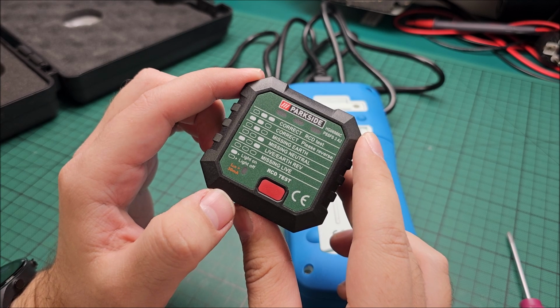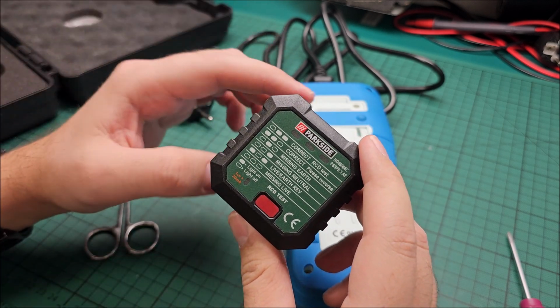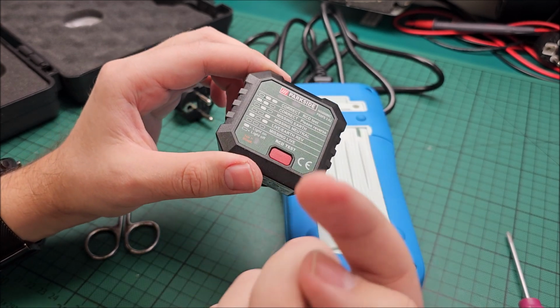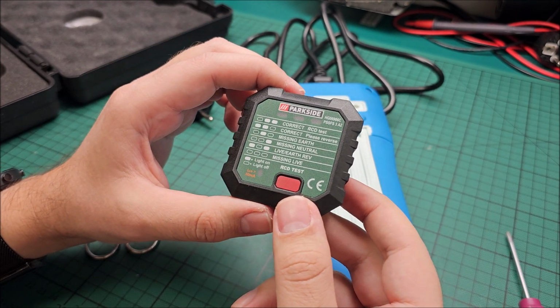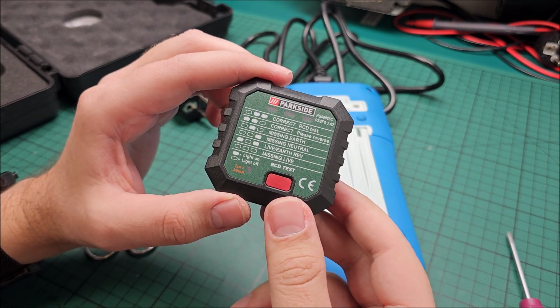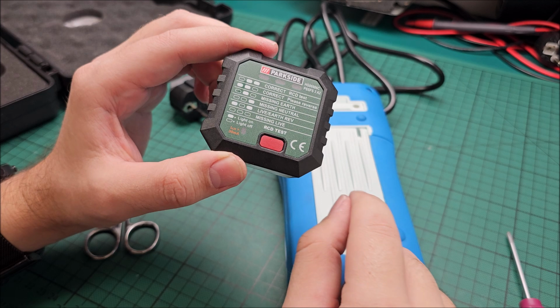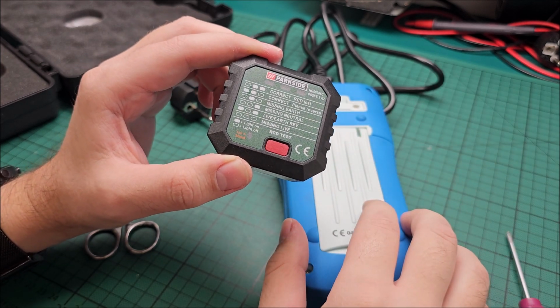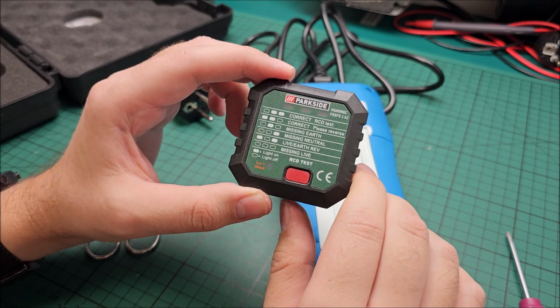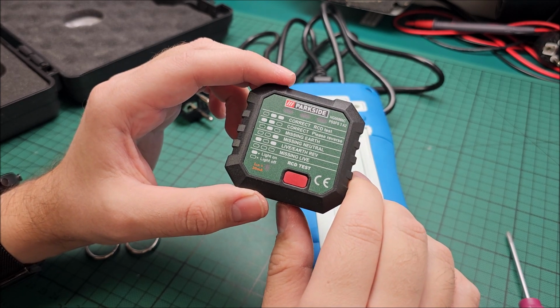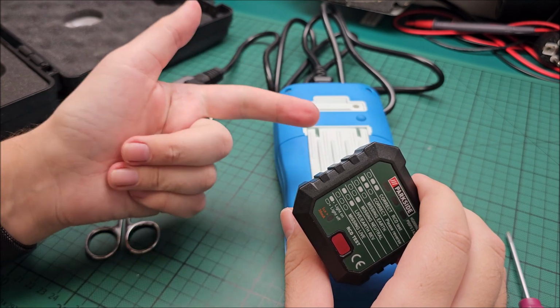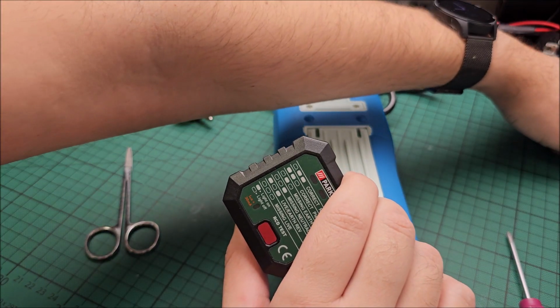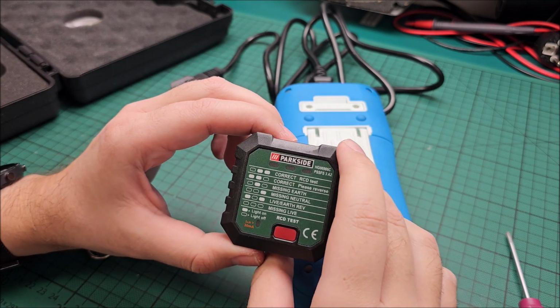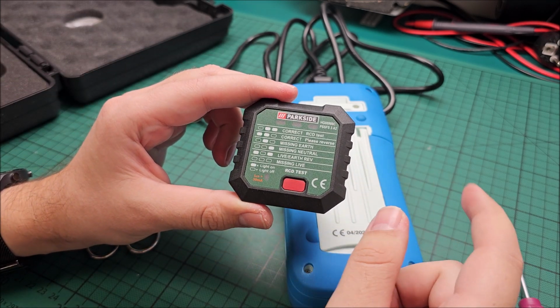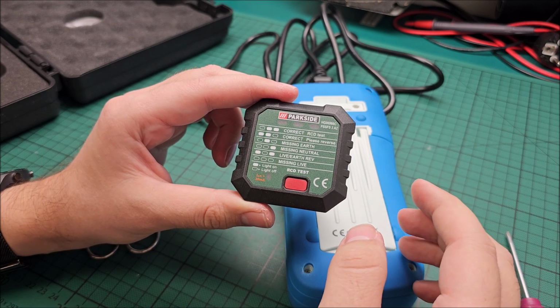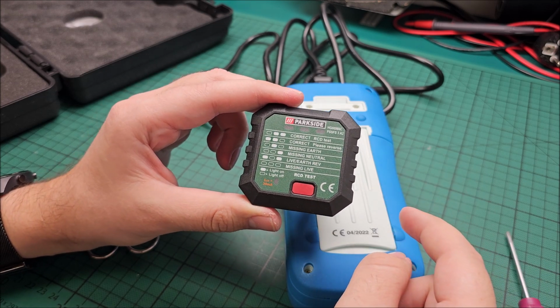Ain't that fishy? To make sure that the 10 milliamp, the 15, not 10, sorry, milliamp, or is it actually a 10 milliamp? I will write on video and clarify that. That one is actually good. I briefly removed from the circuit the main 30 milliamp, and the 10 or 15 milliamp actually tripped, so that one is also good. Then I contacted, I think, Eaton and Schneider, because one is Eaton, one is Schneider, but I tried with other brands, same behavior, and told them, hey, I have two, and the lower value one that is more sensitive is not actually tripping before the main one.